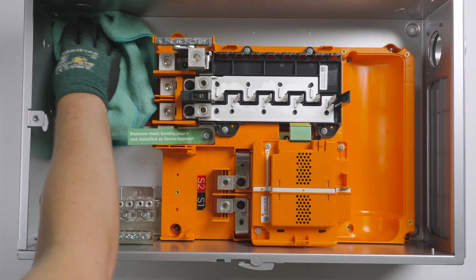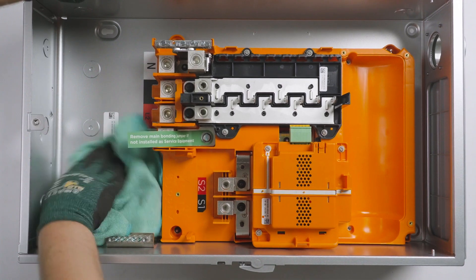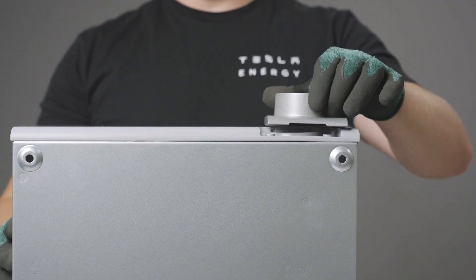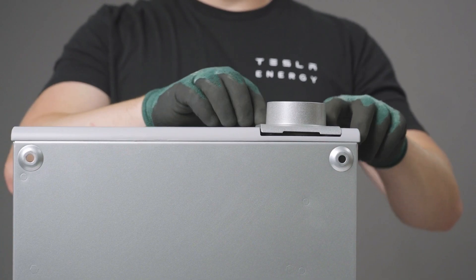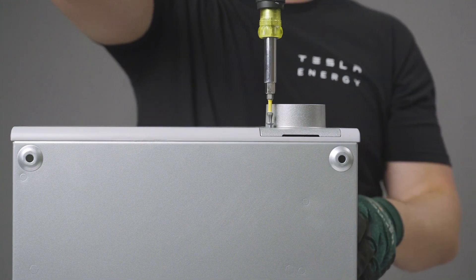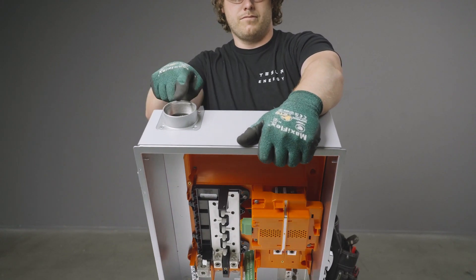Be sure to clean out any metal shavings left behind from drilling into the enclosure. Conduit may only enter the top of the enclosure when using this Tesla-provided conduit hub, available in two different sizes.